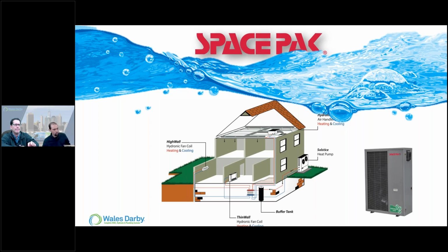That's a good point, and a little tip - with the outdoor unit when we're setting them up, we always set up the system on the refrigerant side based off of the outdoor unit. So we have wherever that manufacturer wants their system to be optimally set. So regardless of 410A, if they're using something else, there will be some changes in TXVs and stuff like that down the road. Right now, it's all 410A. If it's a refrigerant side with a bi-flow TXV, it is heat pump ready.